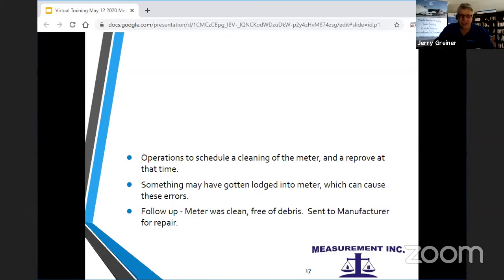We got the operations though to schedule a cleaning. We thought maybe there's something in the meter, that's possible, something lodged in it. And what we found out is the meter was clean, it was totally free of debris. We sent it to the manufacturer, and on this, one of the parts had come loose inside, so they had to take it apart, cut it open, glue the little sensor back onto the tube, and it was all good.